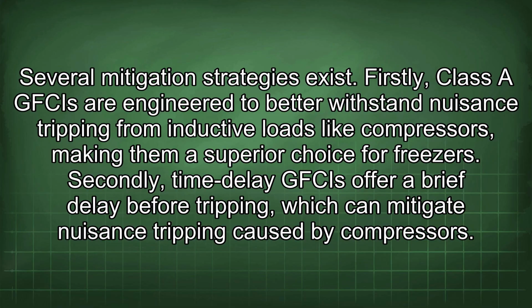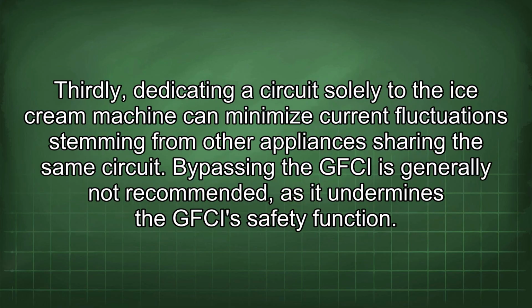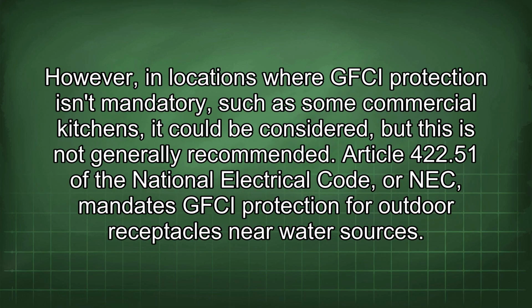Secondly, time delay GFCIs offer a brief delay before tripping, which can mitigate nuisance tripping caused by compressors. Thirdly, dedicating a circuit solely to the ice cream machine can minimize current fluctuations stemming from other appliances sharing the same circuit. Bypassing the GFCI is generally not recommended, as it undermines the GFCI safety function. However, in locations where GFCI protection isn't mandatory, such as some commercial kitchens, it could be considered, but this is not generally recommended.